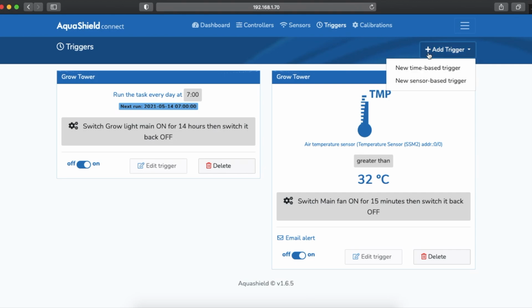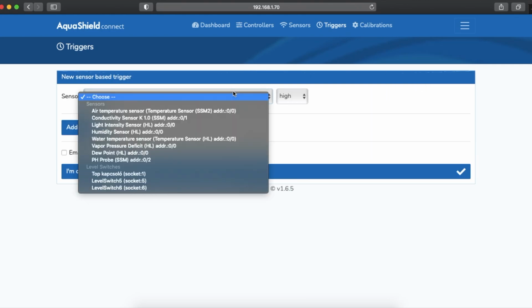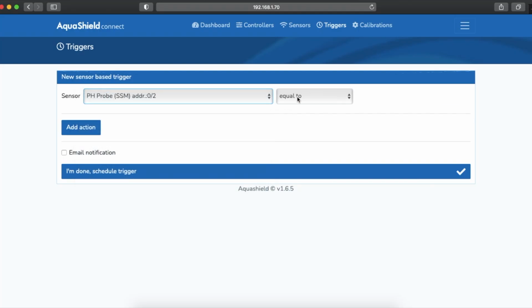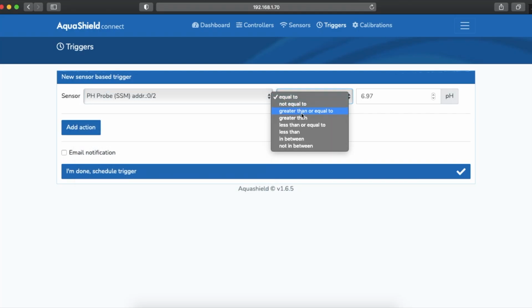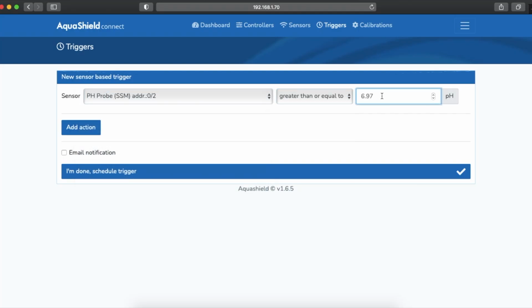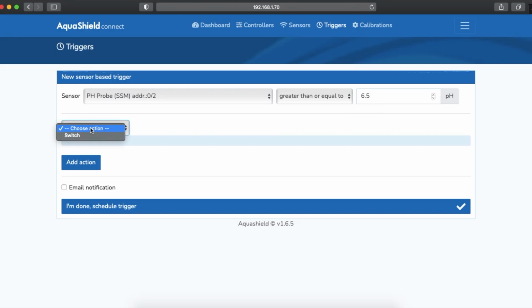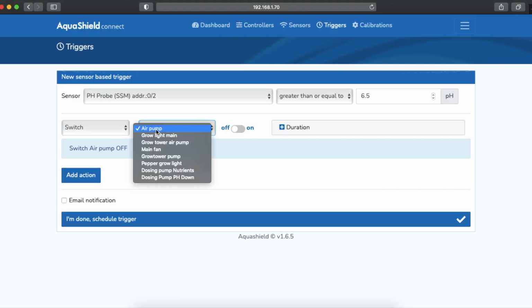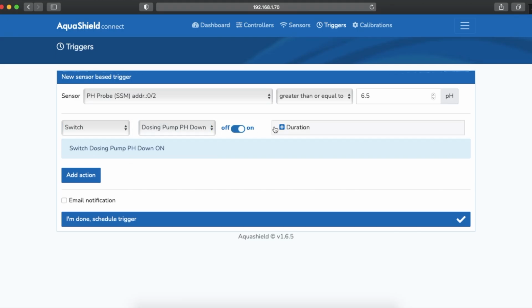Then we set up a sensor-based trigger to run every 30 minutes to check if the pH is higher than 6.5. If it is the case, the trigger will run the dosing pump for 1 minute, adding 15 milliliters pH down to the system. With this, the AquaShield automatically regulates the pH without the risk of overdosing. I also added an email alert, so I will be notified every time the system needed dosing.